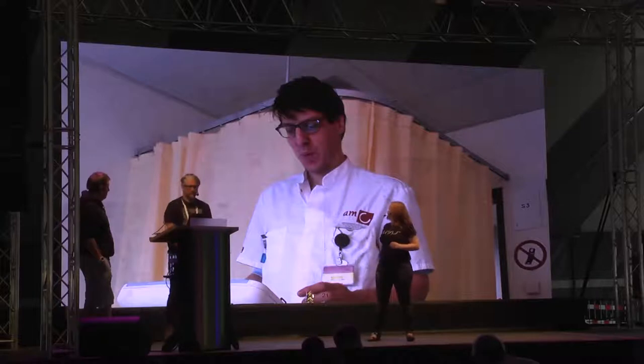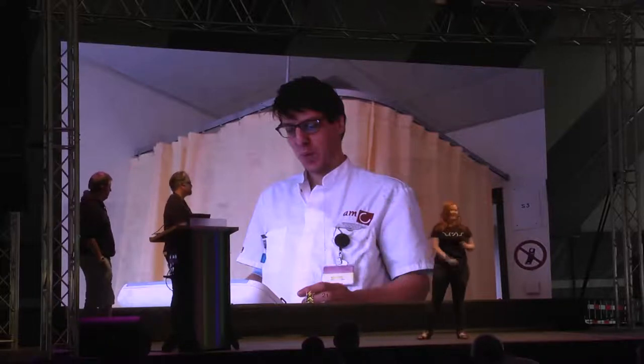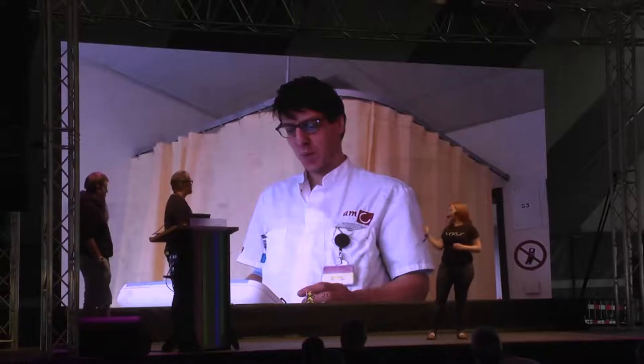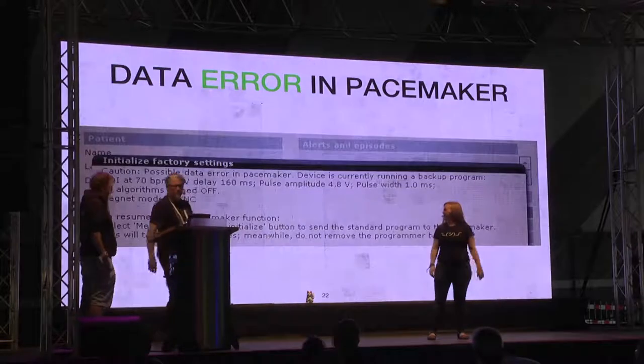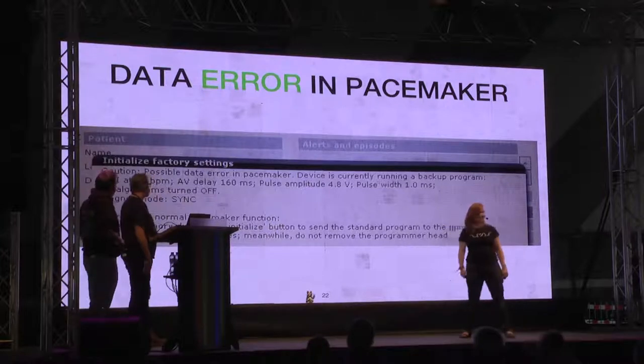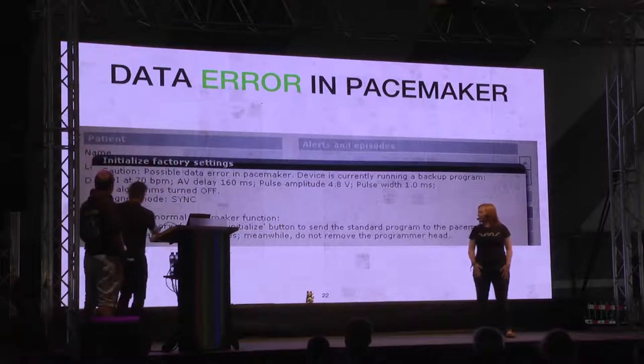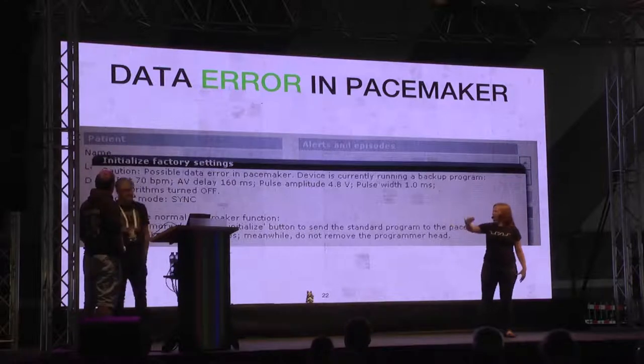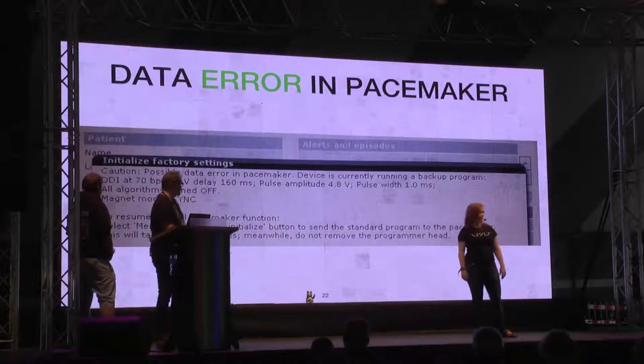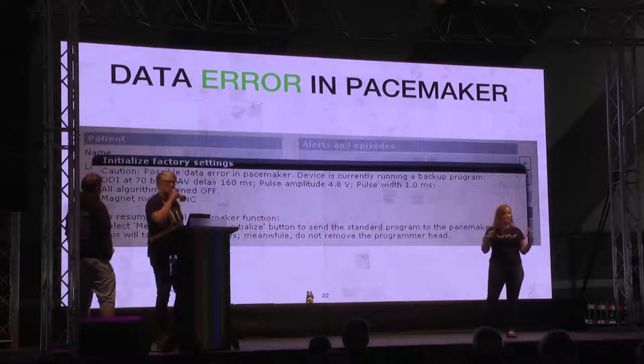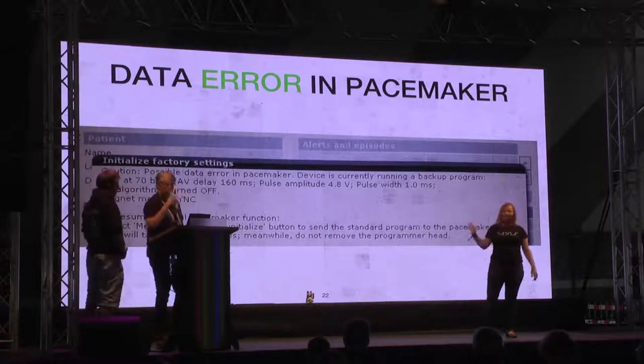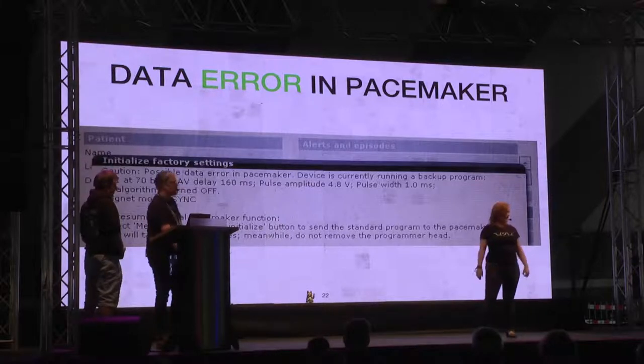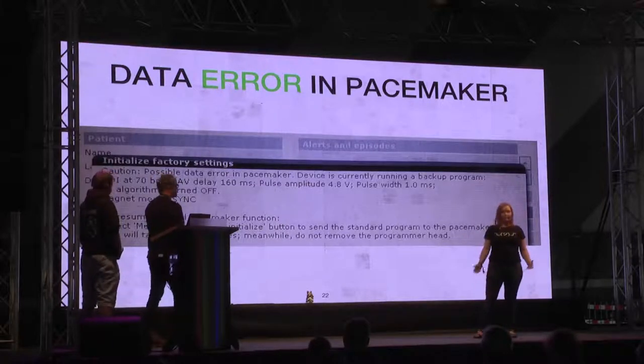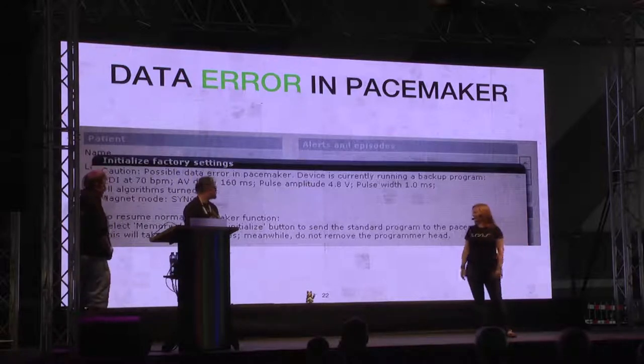So this is the face of the pacemaker technician when he had hooked me up to the programmer and was looking at the display, and he saw this error message. Next slide. So this was actually what had been going wrong - there was a data error in the pacemaker. It had switched up the voltage, that's why I felt the pacing. It was constantly pacing me 70 beats per minute. And I'm really happy that they had engineered in this safety feature, because that was actually keeping me alive. It was a bit uncomfortable, but not a crisis.